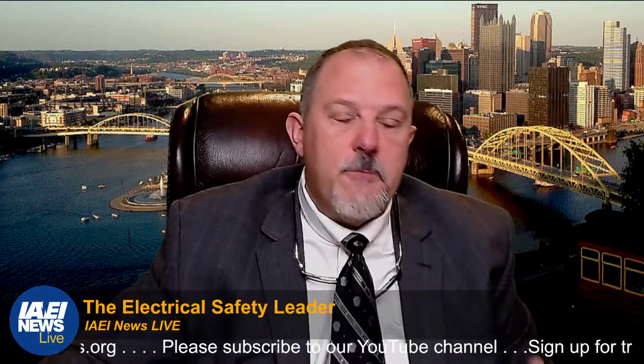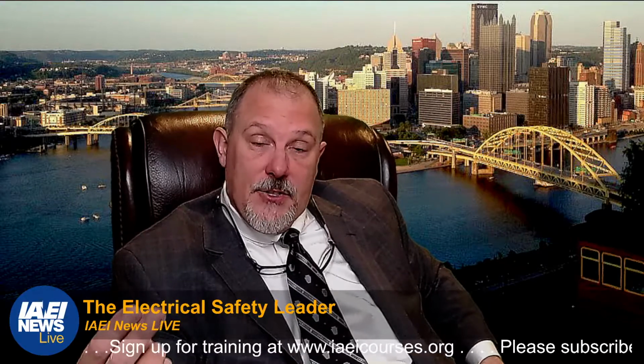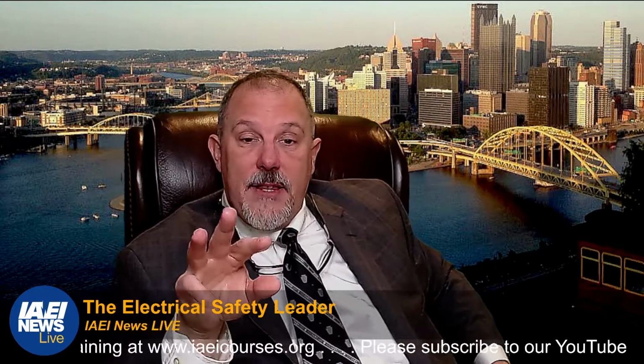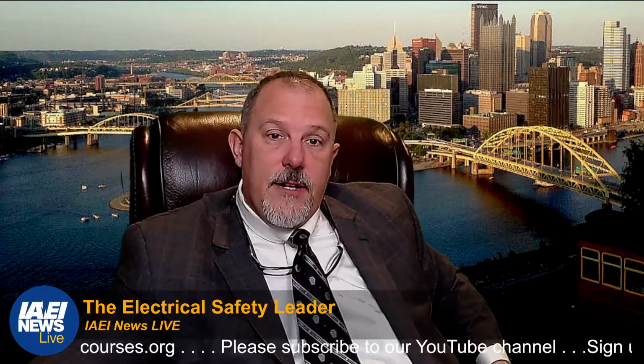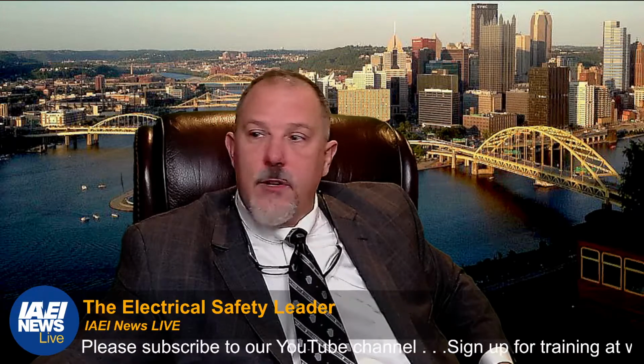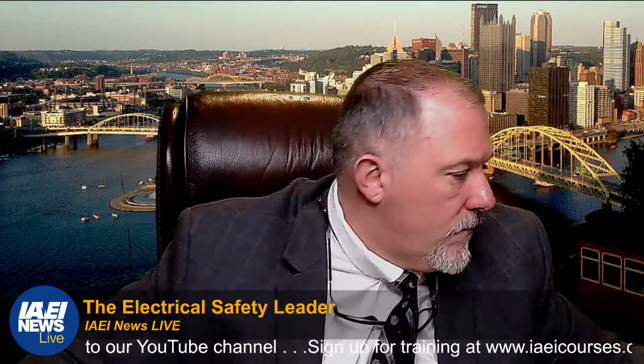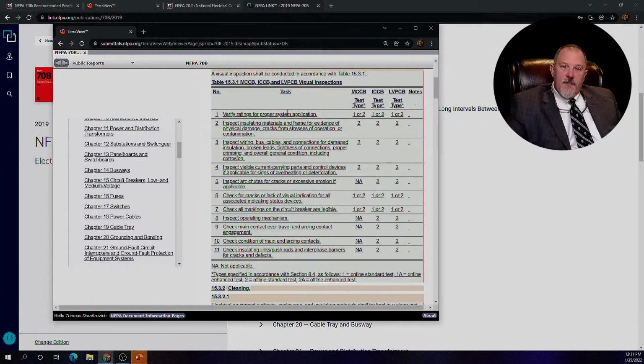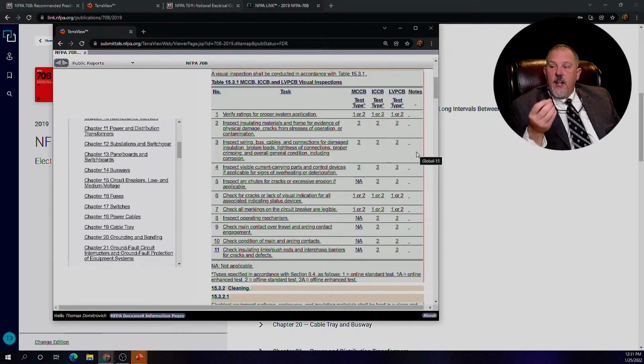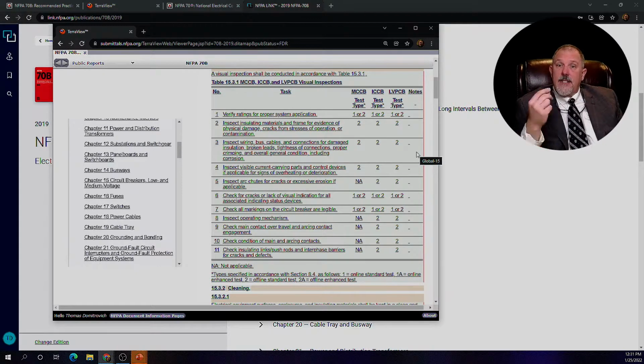So, visual inspections for a circuit breaker. You're going to verify the ratings for proper system application, and this can be done as an online standard test or an offline standard test. Now, we separated the tasks based on... let's do this, I'll just show you what I'm looking at here. So I have verify for proper system application, verify the ratings. We have inspect insulated materials and frame for evidence of physical damage. And you'll see for a molded case circuit breaker, an insulated case circuit breaker, or a low voltage power circuit breaker, all of those have to be done in a condition 2, which is an offline standard test.